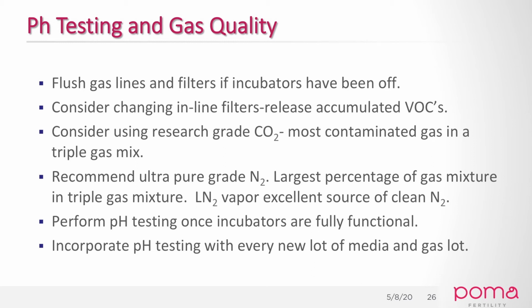The other thing you might want to consider is upgrading the quality of your CO2 and nitrogen, mostly because CO2 is the most contaminated gas in your triple gas mix, and nitrogen because it's the largest percentage of gas in your gas mix. If you have incubators that can mix their own gases and you have your own manifold system, consider using the liquid nitrogen vapor. It's extremely clean, much cleaner than you would ever find in a cylinder. Perform pH testing once your incubators are fully functional, and incorporate pH testing with every new lot of media and gases you get.